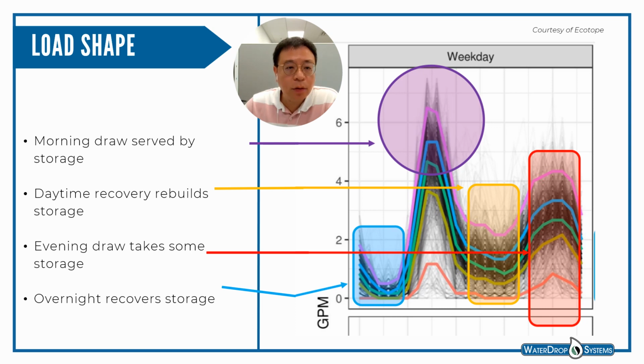The heat demand overnight is low, so the system generates enough hot water and stores it in the tank. When the demand ramps up in the morning, it is served by the storage. After the first peak cycle, the second heat generation is started, until the storage is full, so it prepares for the peak after work.